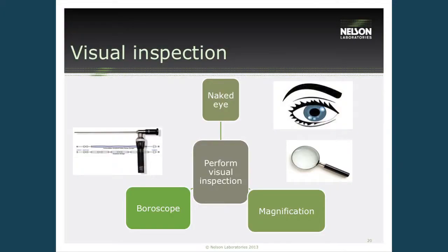Visual inspection is next. After the cleaning procedure, we want to make sure that the devices are free and clear of all soil. One thing to note is that previous guidance documents have stated that we should perform a visual inspection with a naked eye. And now we are looking more at if we should use magnification, using a borescope. How else are we going to see those internal components like the pictures that I showed earlier? So that's getting to be more important. I know a few hospitals have incorporated this into their areas, but very, very few. So they're really relying on the medical device manufacturers to make sure that this happens in their internal labs or test labs, et cetera. So it's a very important part of it.